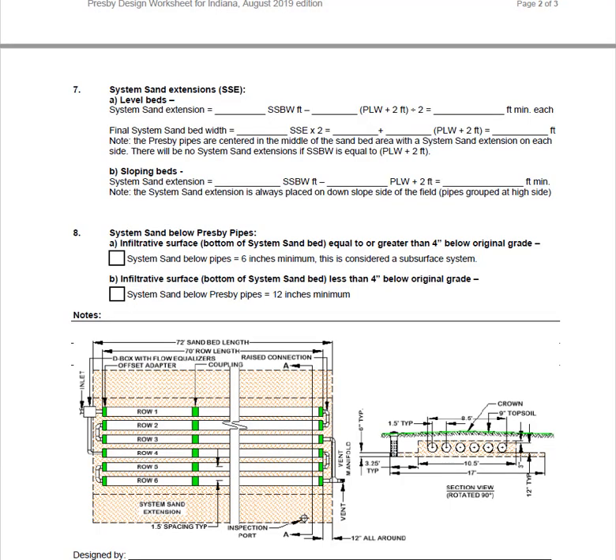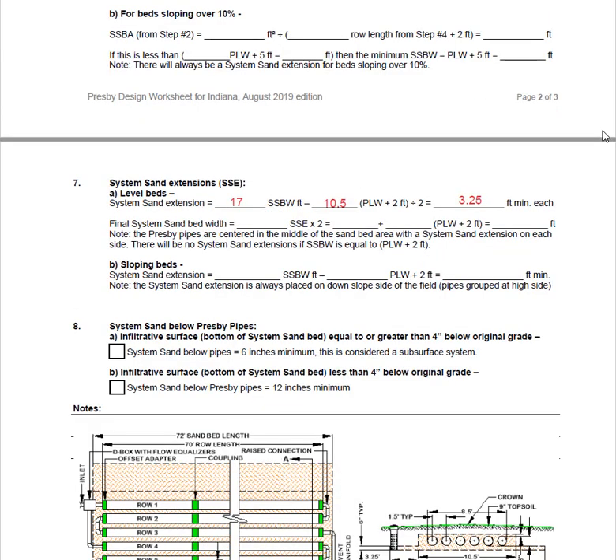Let's determine what our system sand extensions will be. There are two options: A for level beds and B for sloping beds. We will use the level bed option. The first value is our system sand bed width of 16.7 feet, which we will round up to 17 feet for ease of construction. The next value is our pipe layout width plus 2 feet, which brings us to 10.5 feet. We subtract 10.5 feet from 17 feet and get 6.5 feet, which is then divided by 2. This gives us a 3.25-foot system sand extension on each side of the bed. We can verify: 3.25 multiplied by 2 equals 6.5, plus our pipe layout width plus 2 feet of 10.5, confirming our 17-foot final system sand bed width.